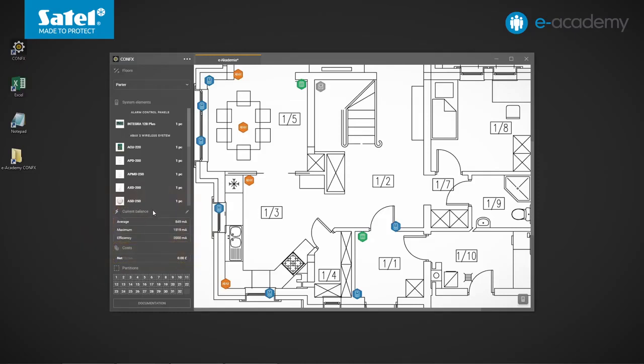You can see three items here that provide quick information about the current demand of the electrical loads as well as the output current of the power supplies at the moment. The value described as average is the sum of the standby current draws of all devices used in the project. Of course, only the parameters of devices consuming energy from the system are counted. No battery-powered devices are included in the current balance.